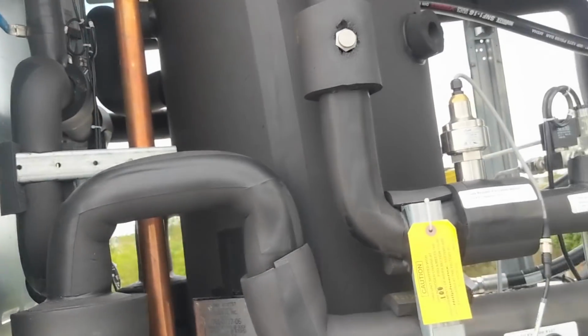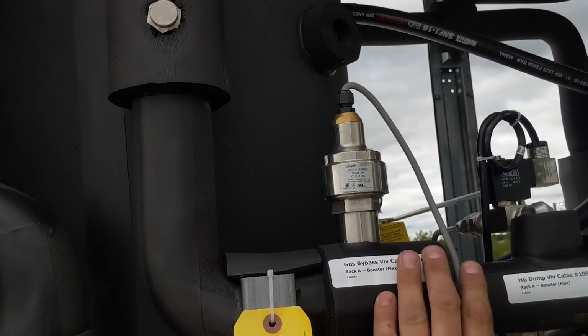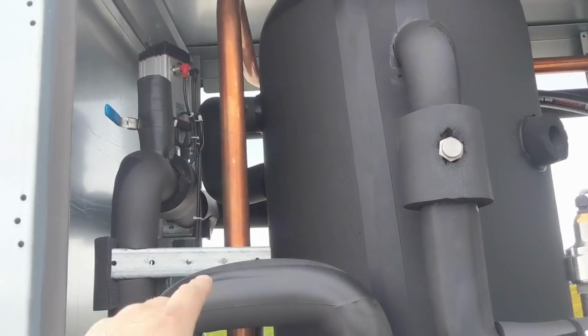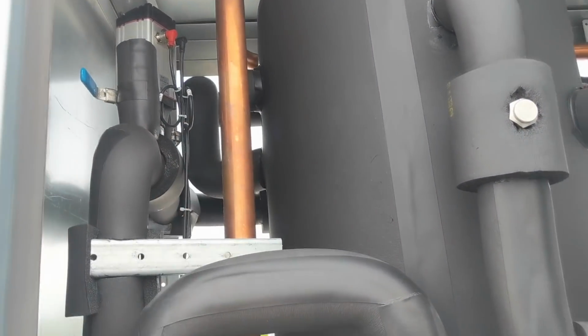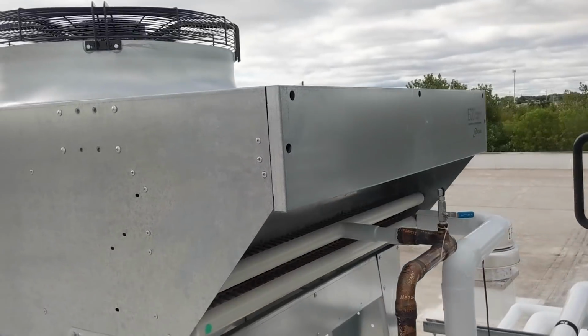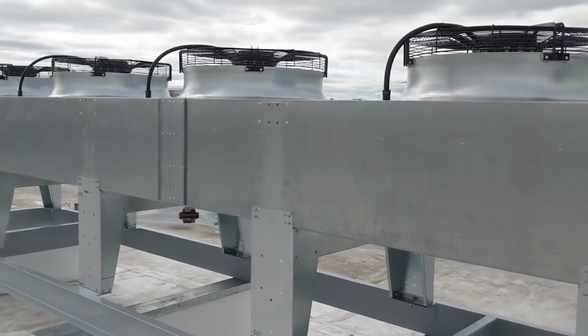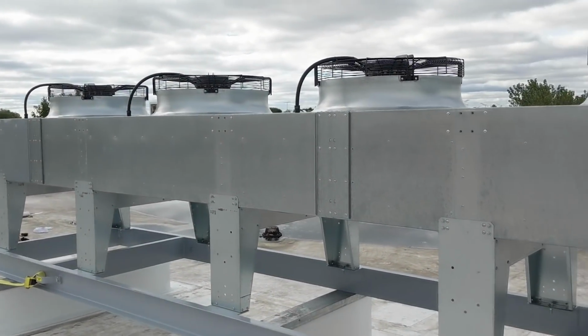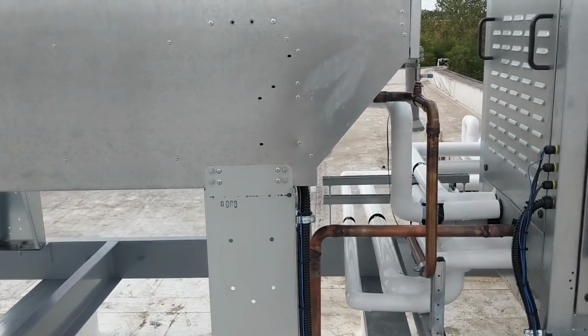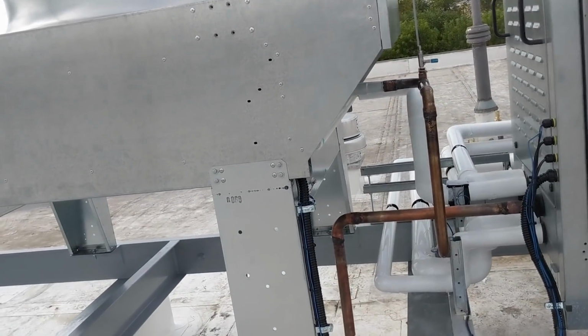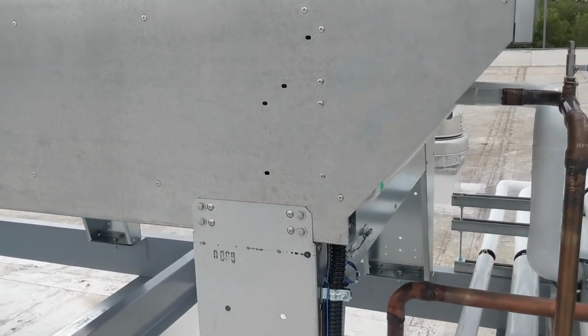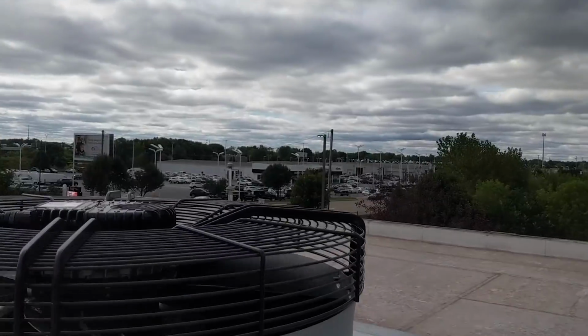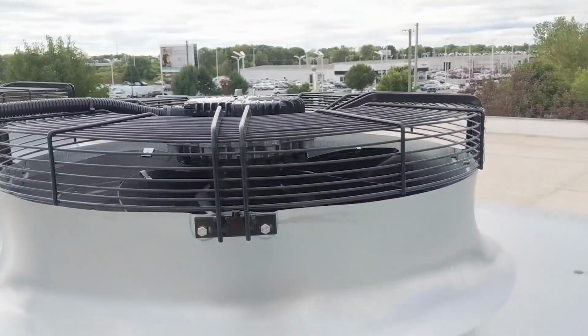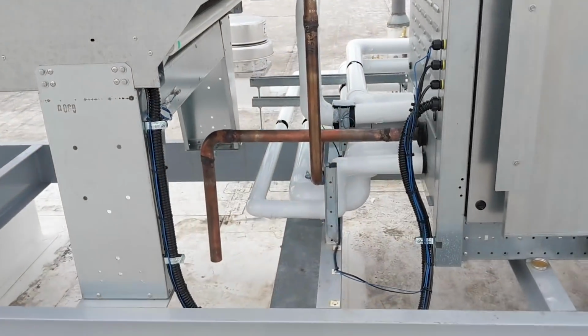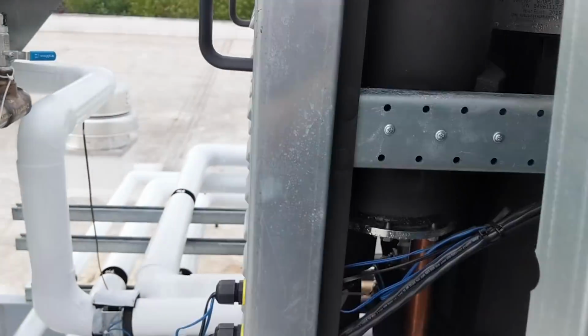We're basically recondensing CO2. When the ambient's low enough, we're barely going to be opening this flash tank bypass valve, and then this is going to start acting somewhat like a holdback valve to keep the pressure up in the gas. This is our gas cooler. So we got a 4-fan ECM gas cooler. Below 87 degrees, it's a condenser. Above 87 degree condensing, it's a gas cooler. It's only cooling gas. So we got our ECM fan motors. They're barely spinning up here. It's only like 50 degrees outside today. That is how the flash tank bypass works.